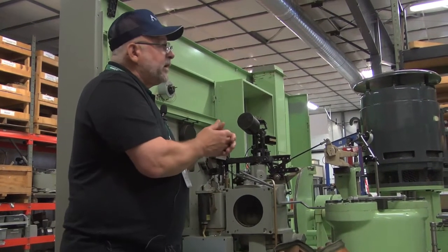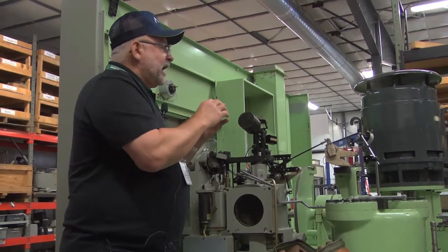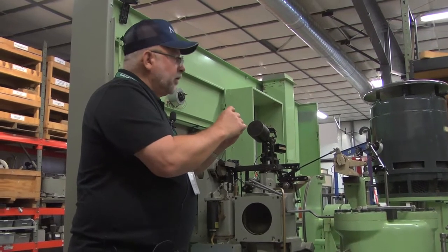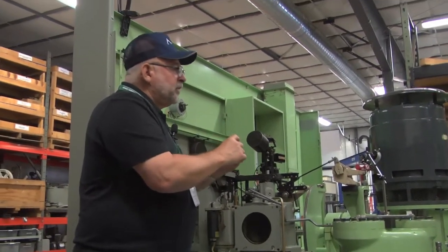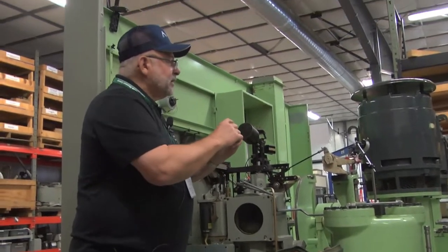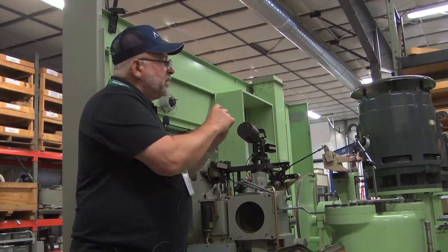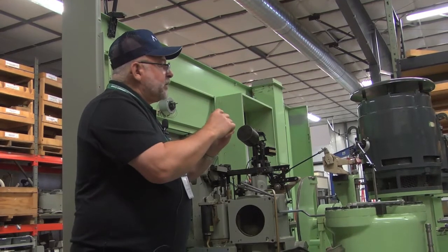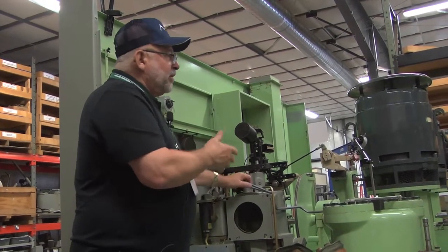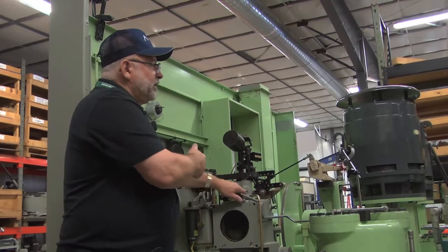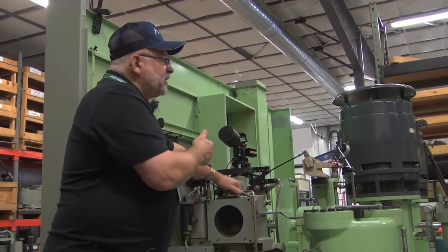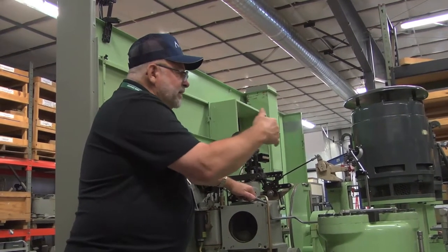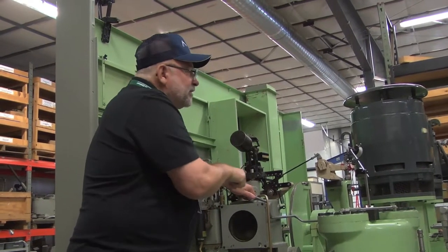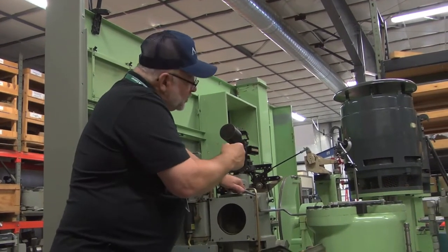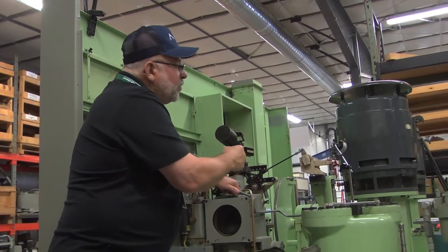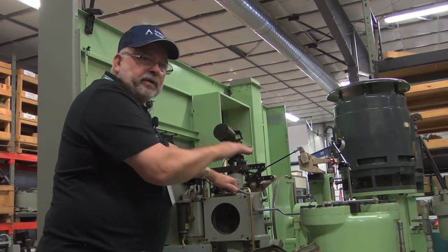PMG. Now, normally all the Woodwards have a name tag on the PMG that shows loaded volts, unloaded volts. Unloaded volts means you had it on a bench, okay? Loaded volts is when it's hooked up to the machine. And it'll tell you the frequency. They don't put one on it, so you've got to see what it is. So normally, I always have it. The guy opens up the cabinet door, the pull-out door, and it's usually written on the inside what it was, so you can see if it's deteriorating.